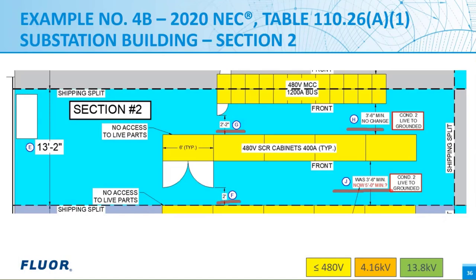So in fact, since these SCR cabinets are individual pieces of equipment and they're less than 1200 amps each, in our opinion, the new sentence that was added, this new requirement would not apply here. Because it's not a 1200 amp rated piece of equipment, even though we have several 400 amp pieces of equipment butted up end to end and it's over 6 feet. So here technically the 3 foot 6 inch minimum is all you still need to comply with the code.